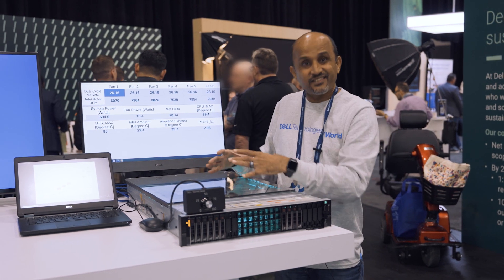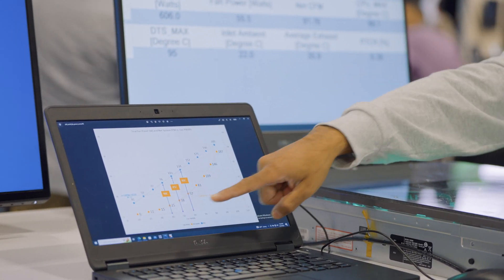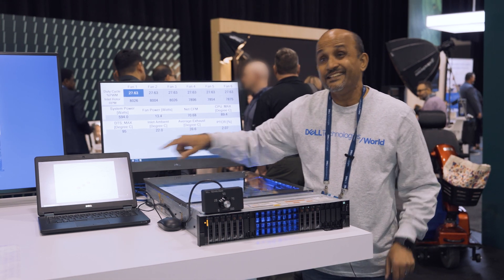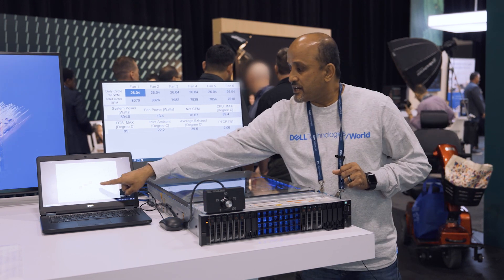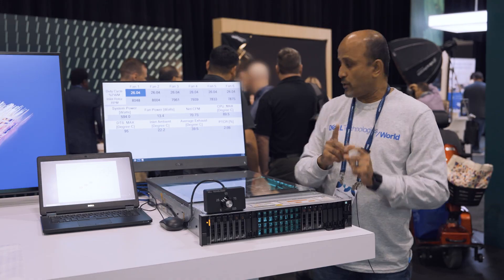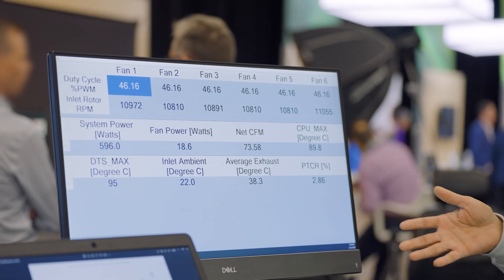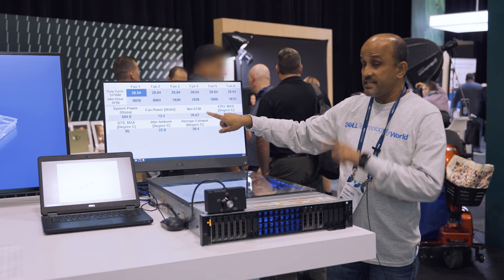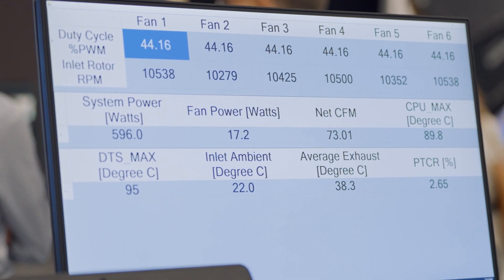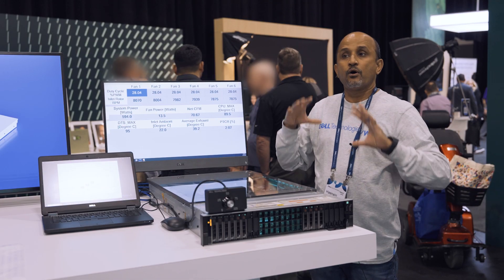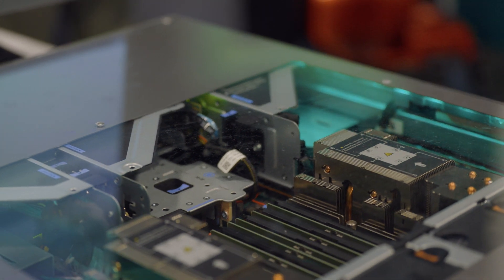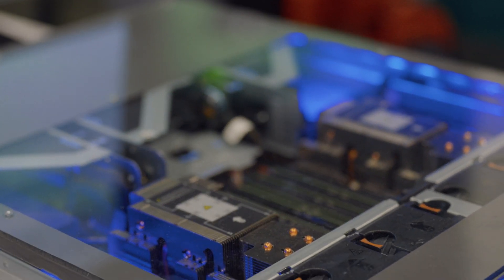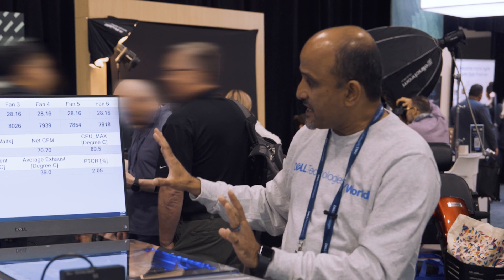You will slowly consume a significant amount of power that is complete waste, which means you will be consuming extra power and extra airflow. We are showing all those numbers here. We are showing what the fan power consumption is, and very uniquely in this area, we display the net airflow coming out of the box. No OEM or ODM actually does that, and that's useful because you can use that to size your cooling in the data center.